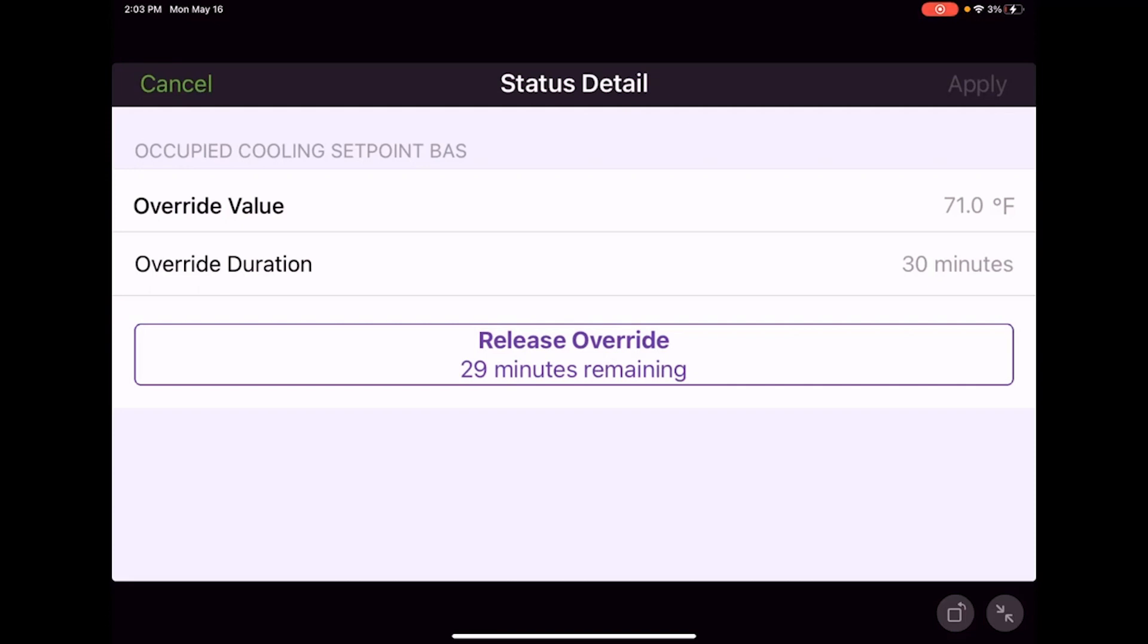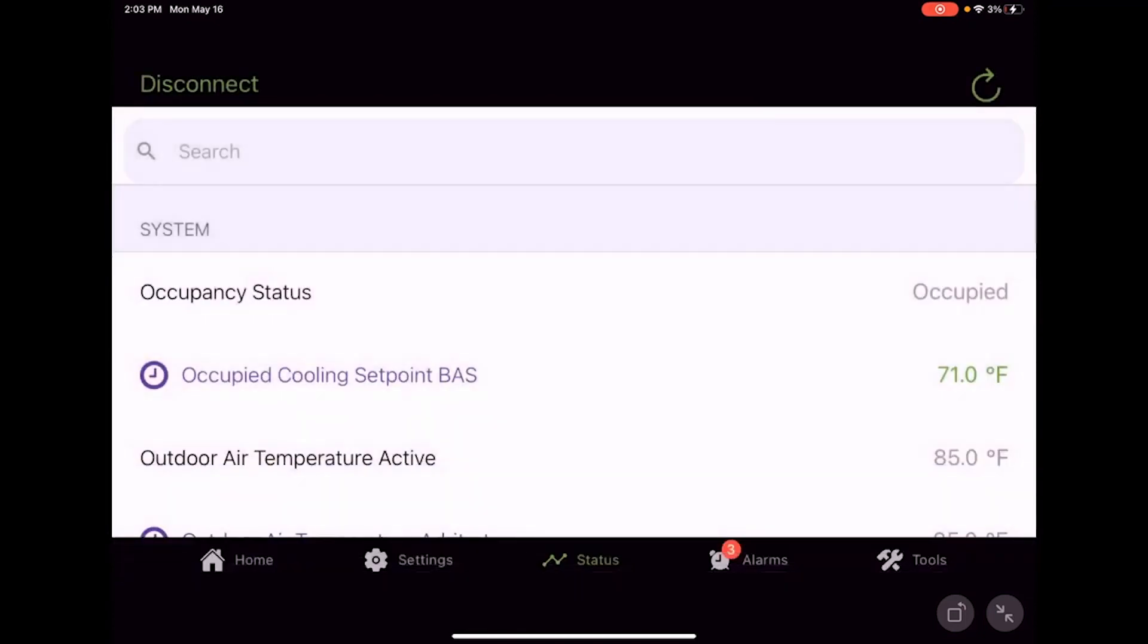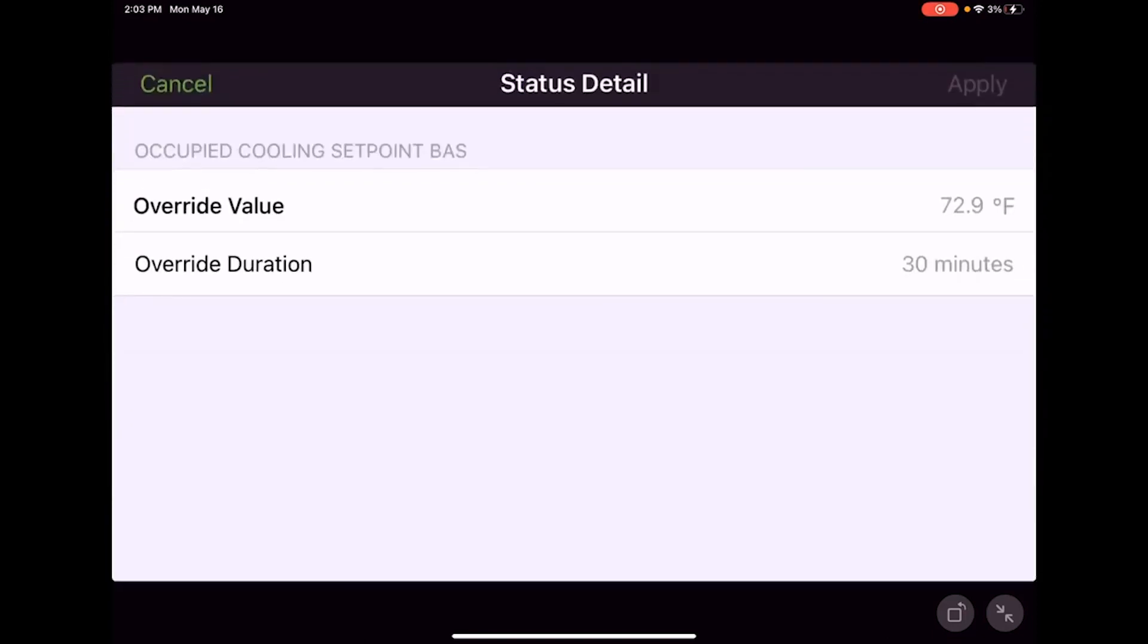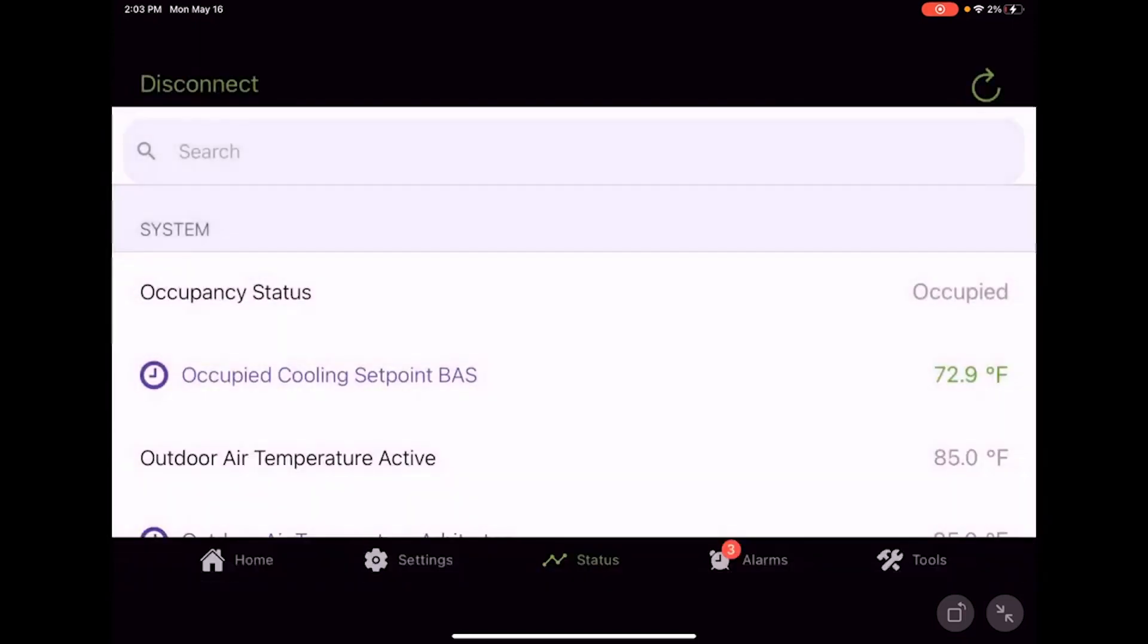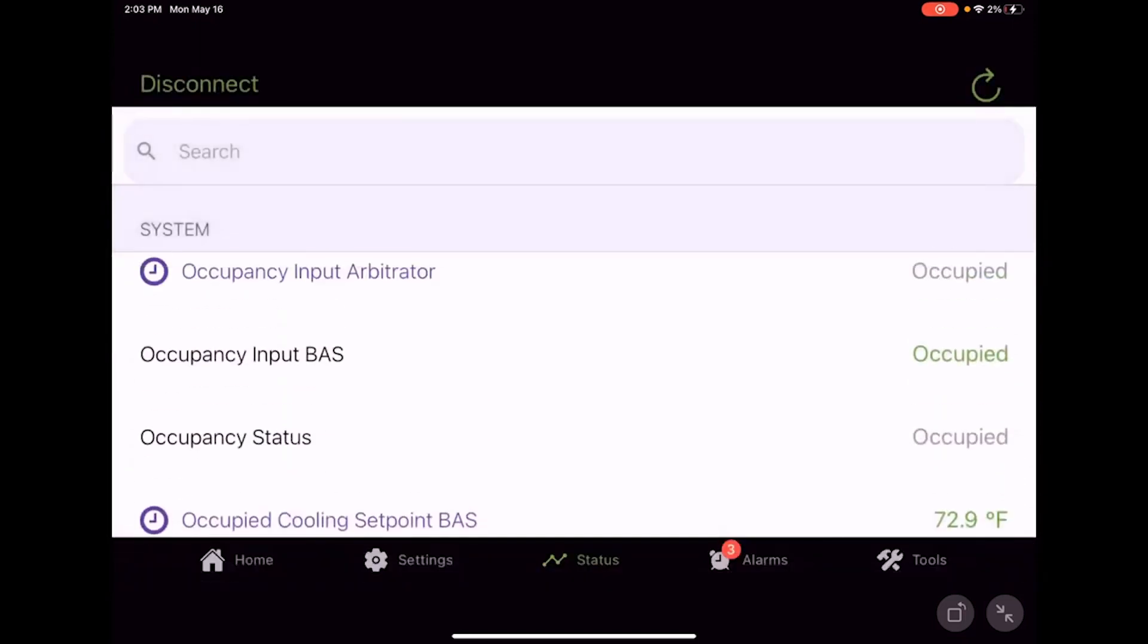If we don't want to wait 29 minutes, which we don't because we don't want this to be a 29-minute video, we could actually just hit release override. Now that override's released, we see it went back to 72.9. If we click back into it, we notice there's no override present on that particular point.